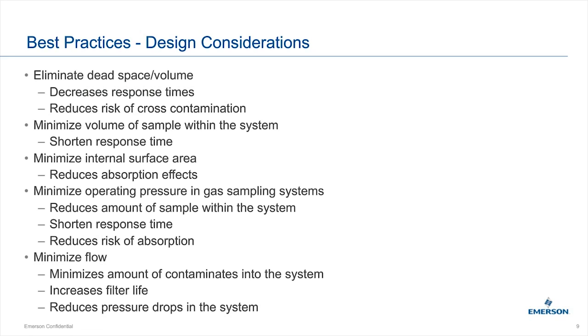Regarding flow: this is nuanced — you'll hear us say both minimize and maximize flow. It's quasi-dependent on the situation. At the probe, if the sample loss into the probe is higher than what's flowing in the pipe, it acts like a vacuum and sucks contaminants in, increasing filter maintenance burden. If you go too slow, you increase lag time, and with liquids you get particle dropout. The best word is really 'optimize' rather than minimize.